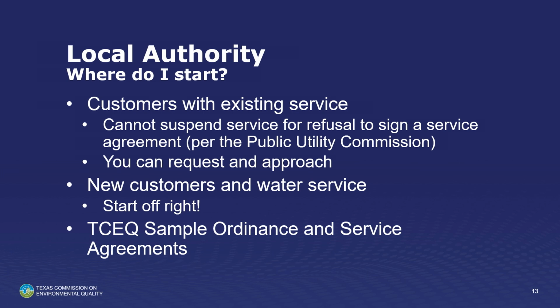It's a good question. Customers with existing service cannot have service suspended for refusal to sign a service agreement, by the Texas Public Utility Commission. This is very important. If you're starting a program and you've got people out there, you cannot cut their water off if they refuse to sign that service agreement. So the only thing I know you can do is go out there and be very nice, talk to them, and explain to them what backflow is and everything like that. So you have to be a pretty good salesman with some people, no doubt.